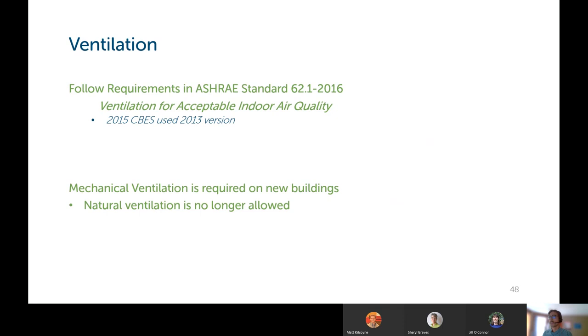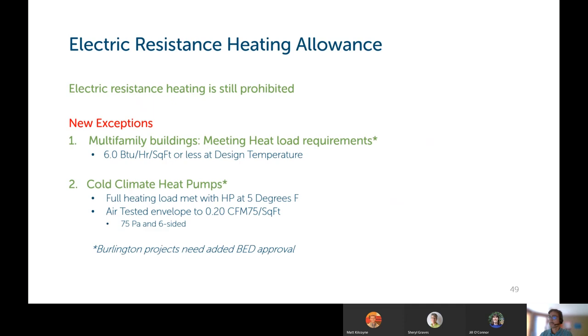So for ventilation, you must follow requirements of ASHRAE standard 62.1 version 2016. That is the ventilation for acceptable indoor air quality standard. The 2015 version of the commercial energy code used the same standard, but the 2013 version. So this has been updated to 2016 for the 2020 commercial energy code. Part of this change is that mechanical ventilation is now required on all new buildings. Natural ventilation is not allowed in ASHRAE standard 62.1 2016.